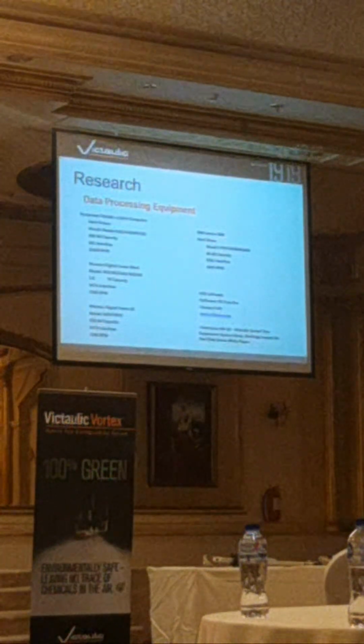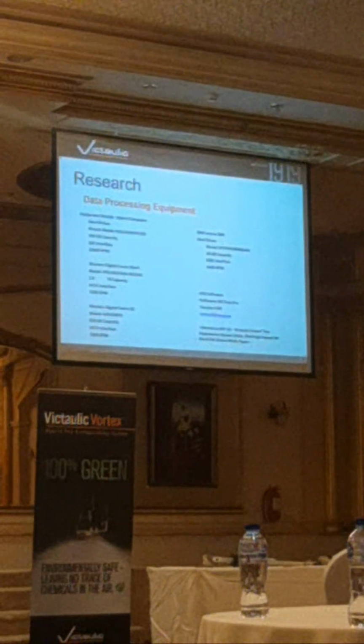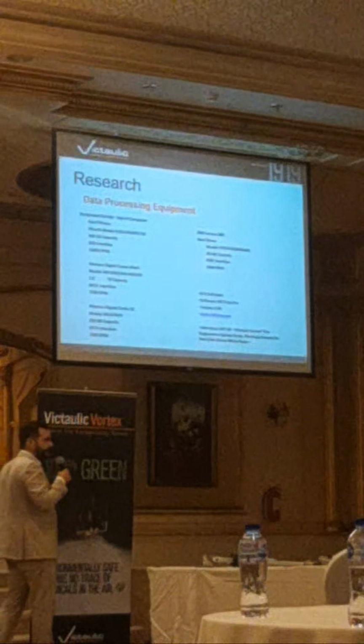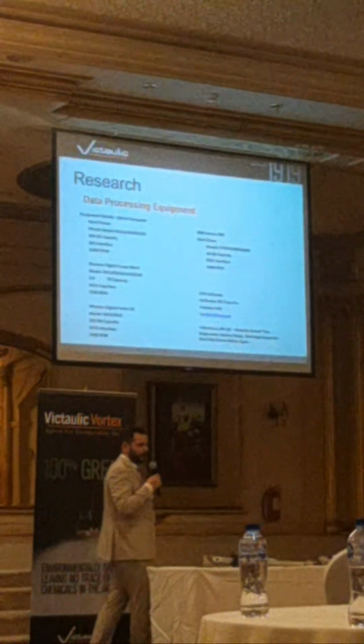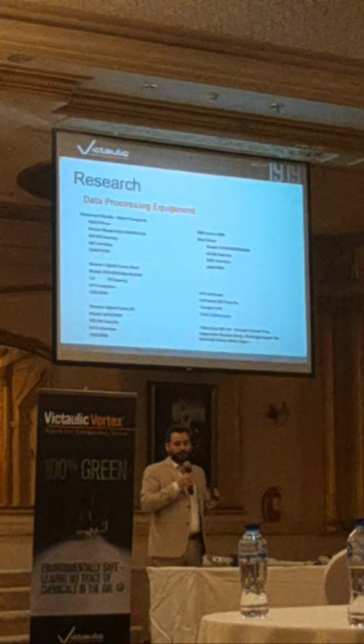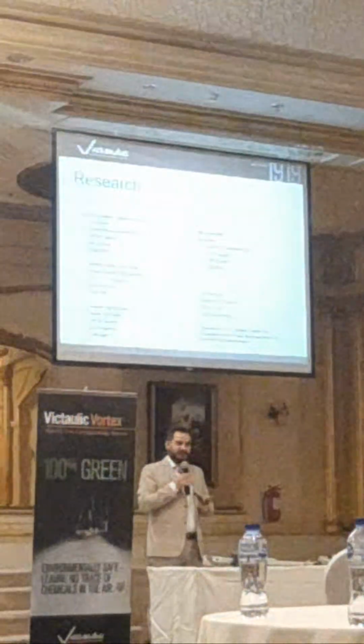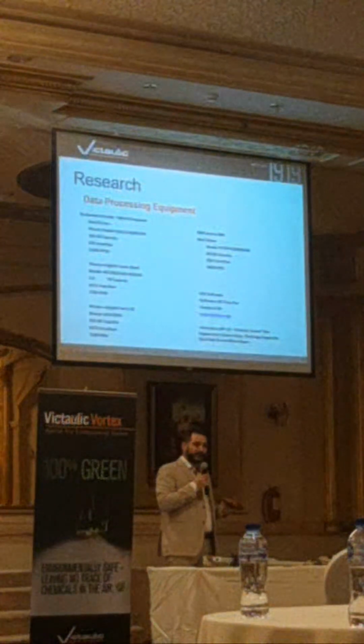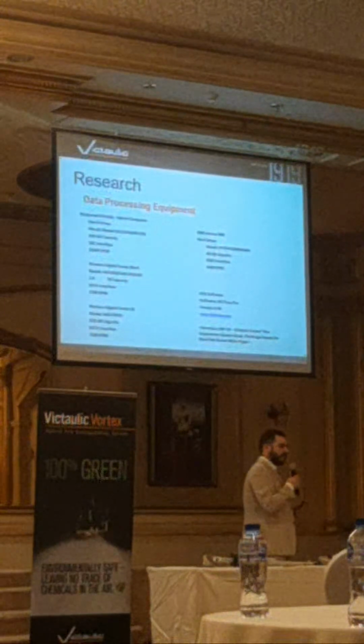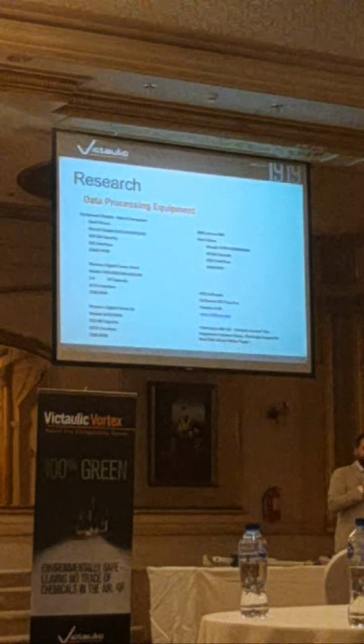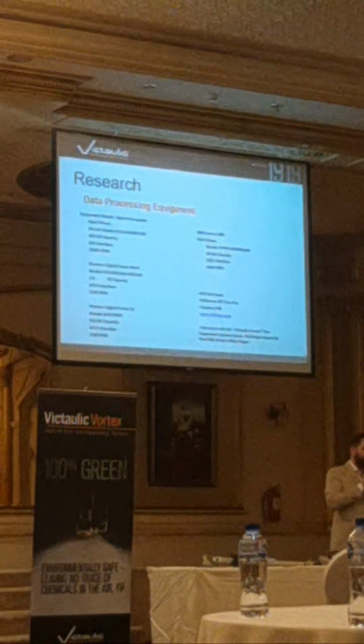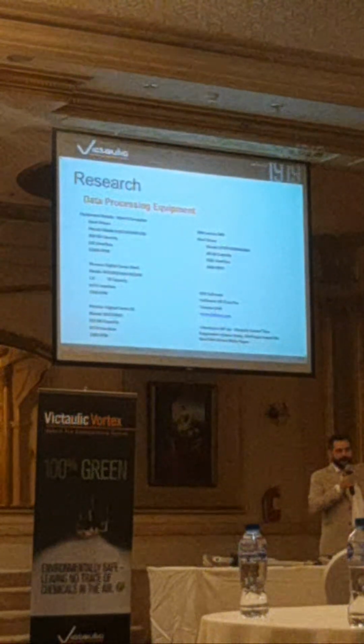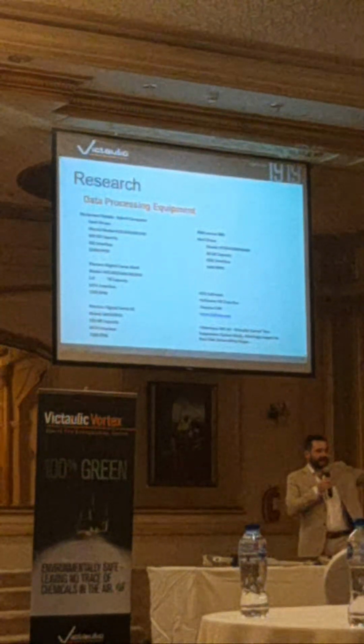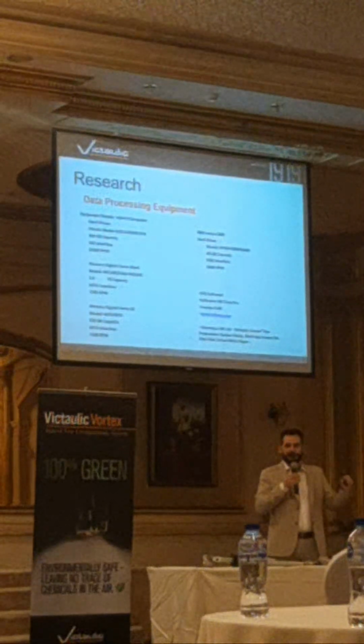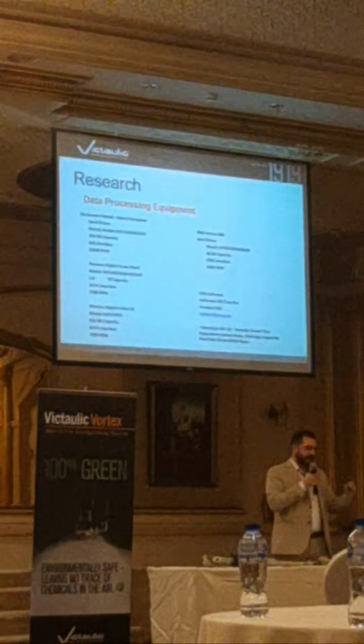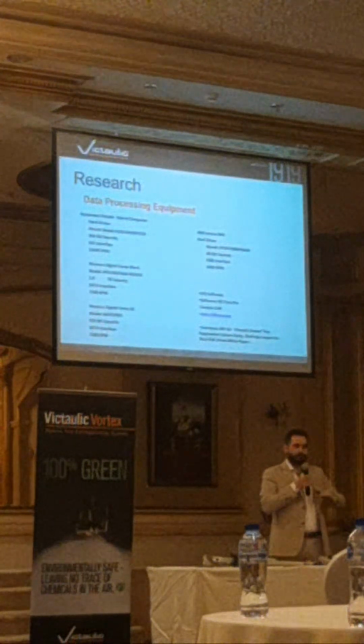Other research we've done besides FM: some of you might know the inert gases had an issue. This was in 2008, in a Scottish server room or data center, where the fire protection system discharged and the complete server room broke down. It was completely destroyed, a governmental building. They investigated and found that the frequency and pressure of the Inergen system when it discharged matched the frequency of the hard disk drives installed in that data hall. Because of this, they went into resonance and completely broke down.